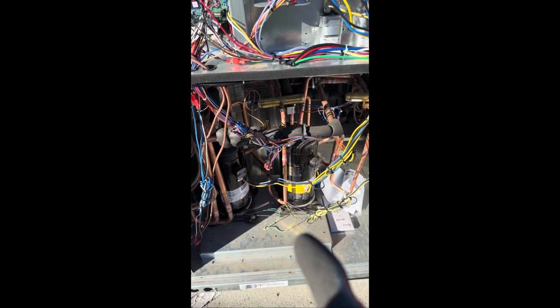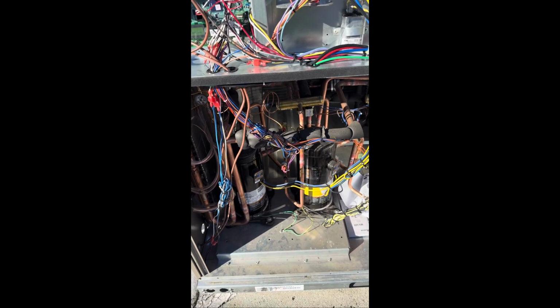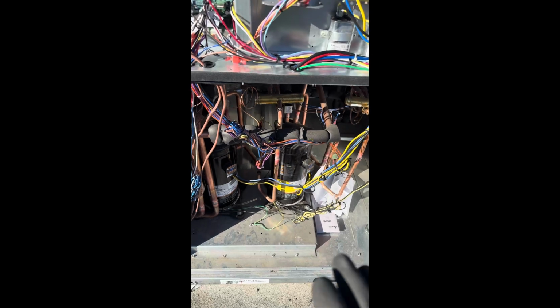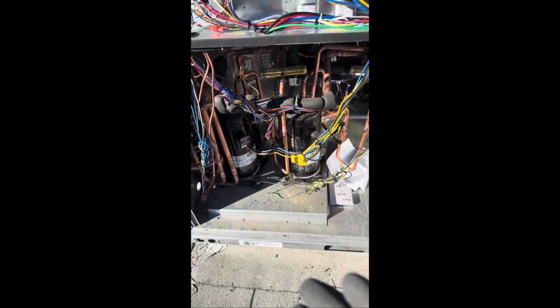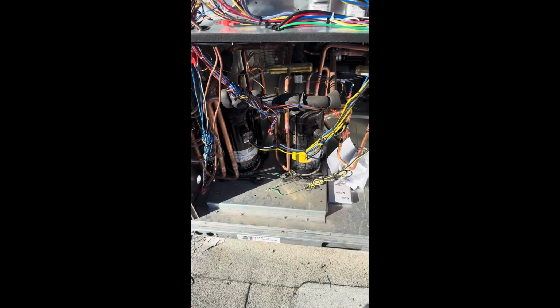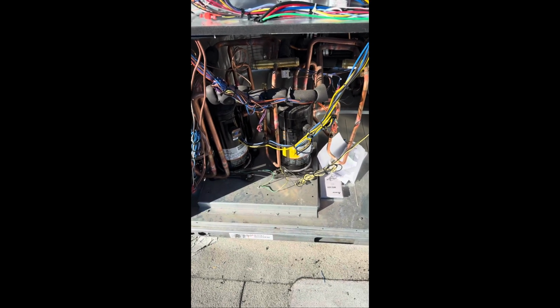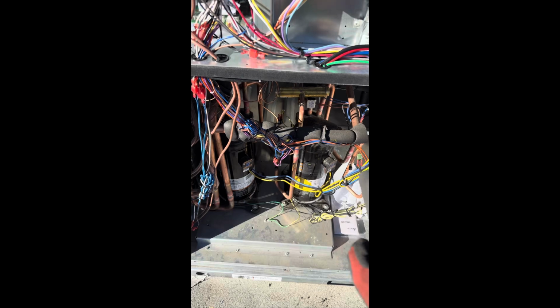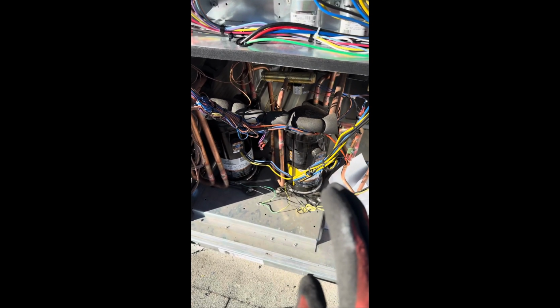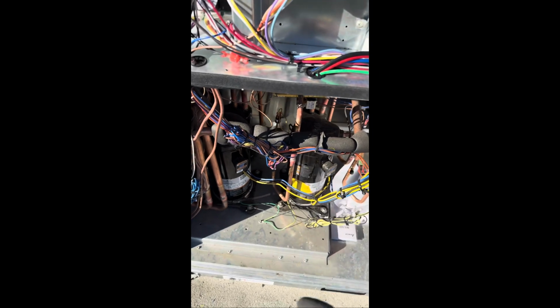So now the next thing we're gonna do here is we're gonna check the rotation of this compressor, which I've already done beforehand. So there's 2 ways that generally a lot of people like to do it. Some people like to recognize the sound of it running backwards. I don't really recommend that. Sometimes you can leave it running and people think, yeah, it sounds okay. I don't recommend it. I always hook up my gauges to it to make sure that it is actually pumping the correct way in either heating or cooling mode.